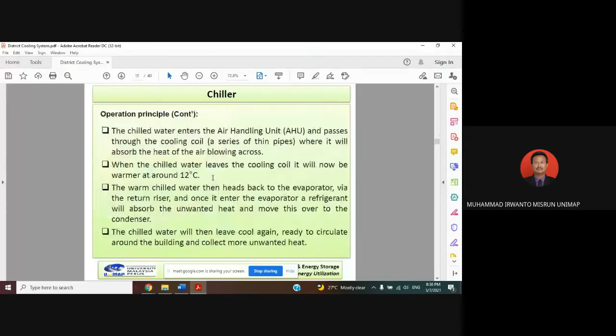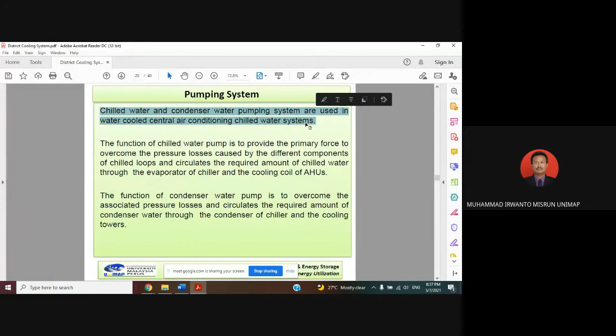Chill water and condenser water pumping systems are used in water-cooled central air conditioning chilled water systems. The function of the chilled water pump is to provide the primary force to overcome the pressure losses caused by the different components of the chill loop, and circulate the required amount of chilled water through the evaporator of the chiller and the cooling coil of the AHU. Later we can look at it and I'll explain again.